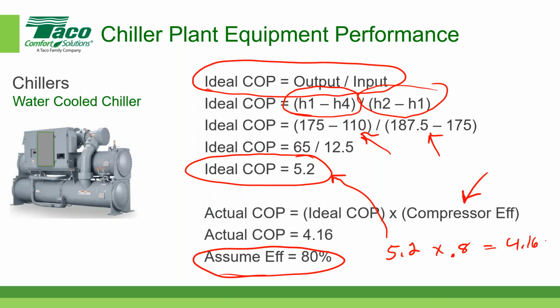The important thing to keep in mind is that, again, repeating what I said a moment ago, the enthalpies are a function of temperature and pressure when it comes to the compressor and the evaporator. So the ideal coefficient of performance, the capacity essentially of the chiller, is a function of these temperatures and pressures, and they are independent of the compressor efficiency. As soon as you add the compressor efficiency, that's when you talk about the actual coefficient of performance.